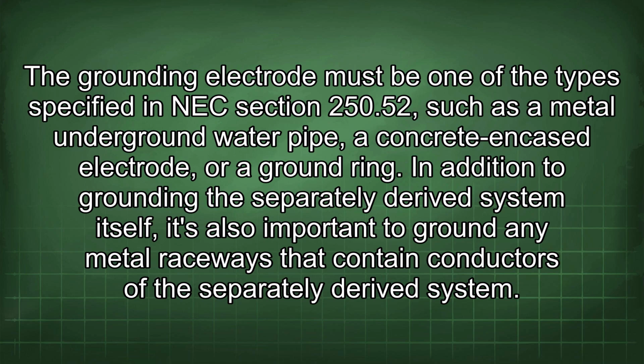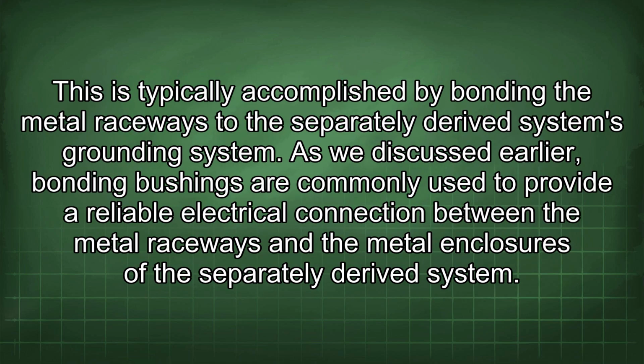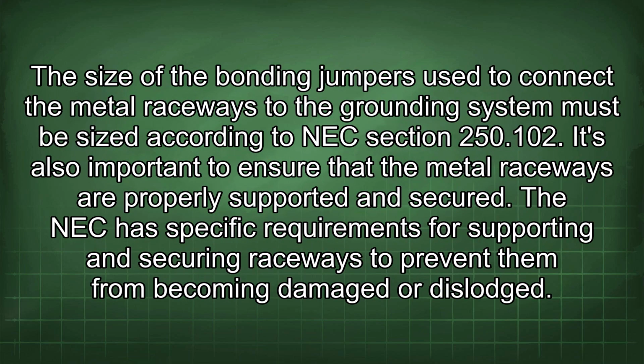In addition to grounding the separately derived system itself, it's also important to ground any metal raceways that contain conductors of the separately derived system. This is typically accomplished by bonding the metal raceways to the separately derived system's grounding system. As we discussed earlier, bonding bushings are commonly used to provide a reliable electrical connection between the metal raceways and the metal enclosures of the separately derived system. The size of the bonding jumpers used to connect the metal raceways to the grounding system must be sized according to NEC section 250.102. It's also important to ensure that the metal raceways are properly supported and secured. The NEC has specific requirements for supporting and securing raceways to prevent them from becoming damaged or dislodged.